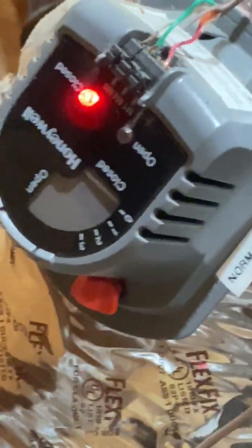I have 3 thermostats, so the board thermostats get tied to the board, then it decides which one of the zones and control valve for the zone gets opened or closed. Okay. Now, in my situation, I go against probably the rules, but it just doesn't make any sense to me. I come from a background where I had a baseboard hydronic hot water system, and you didn't run hot water to zones that didn't need heat.